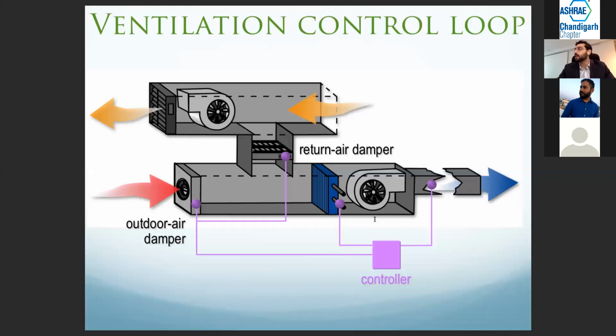Let's look at the next one, the ventilation control loop. In this scenario, we are going to take care of the ventilation. Now we've added a couple more sensors, and we're controlling the outdoor air damper and the return air damper. We are going to be modulating the outdoor air damper and the return air damper to create a mixed air temperature that we require, which will then go through the coil. Then we will detect the temperature, and we may tell the coil or the valve to open or close based on what we need, and achieve the sequence that way. So far, so good. Great.